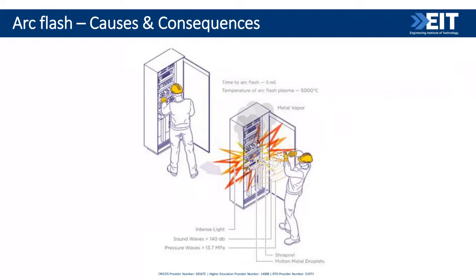Looking at this image — the time to an arc flash, we're talking milliseconds. In this particular example, five milliseconds is the typical time when an arc flash occurs from the fault to the flash — very, very quick. In this picture, you've got a worker working on a switchboard. The switchboard is obviously live, the panel is open, and we have an arc fault. We've got that intense light, sound waves greater than 140 decibels, pressure waves, metal vapour because metal is being vaporised, shrapnel, and molten metal droplets all blasting out of that switchboard to someone standing in front of it.